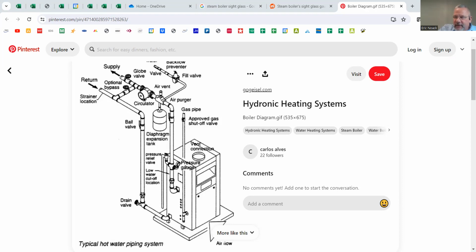So what you see there then is a diaphragm expansion tank. And that is the modern way of handling that expansion. The other way that you're going to see that's not shown here is called a compression tank. And this is a large tank. It's a big cylinder that's usually up in the floor joists of the building that the boiler is in. So it's above you, and the piping goes up to that. And the way that works is essentially just by gravity. The air goes up and it gets trapped into that tank. And it maintains some air, and that's the cushion. The air that's in that tank up high is the cushion for the expansion that's going to occur when the water heats up or cools down.